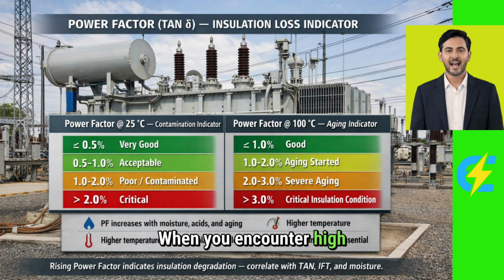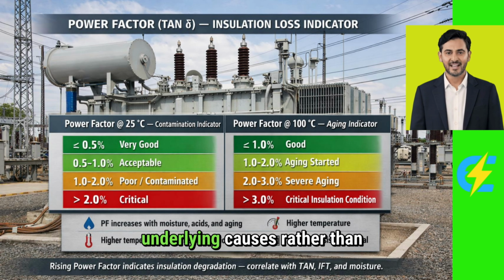When you encounter high power factor readings, especially at 100 degrees, you need to take corrective action. First, identify the root cause. Is it moisture ingress due to poor sealing? Is it oxidation due to overheating or poor inhibitor levels? Is it contamination from external sources? Then improve moisture control systems, consider oil reclamation or replacement, and address the underlying causes rather than just treating symptoms.